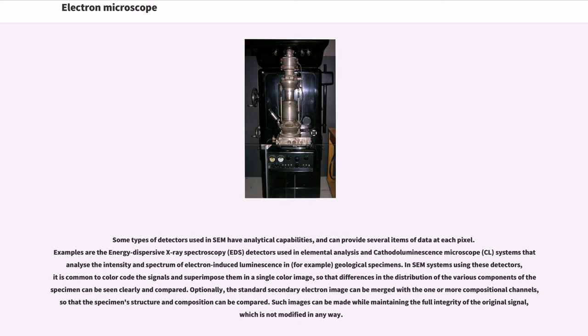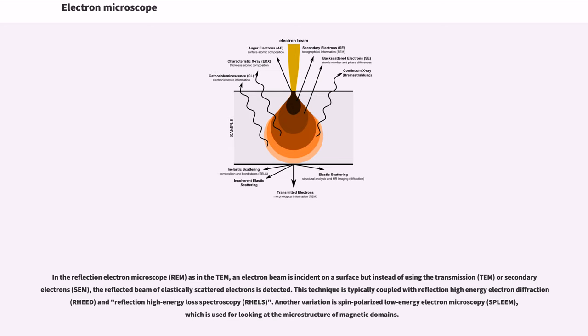Optionally, the standard secondary electron image can be merged with the one or more compositional channels, so that the specimen structure and composition can be compared. Such images can be made while maintaining the full integrity of the original signal, which is not modified in any way.